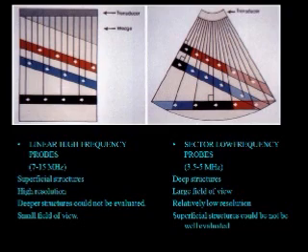Now another thing is this sector probe. Here we use a low frequency probe generally 3.5 to 5 megahertz and we can use it to image the deeper structures. The advantage is that we have a large field of view but as I told you the resolution is low and the superficial structures could not be well evaluated.